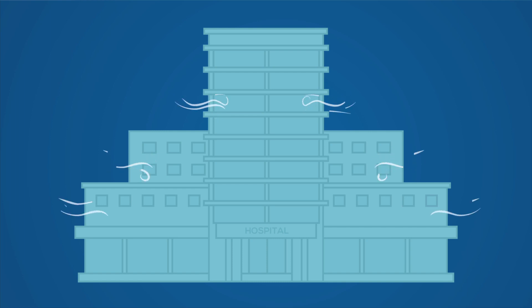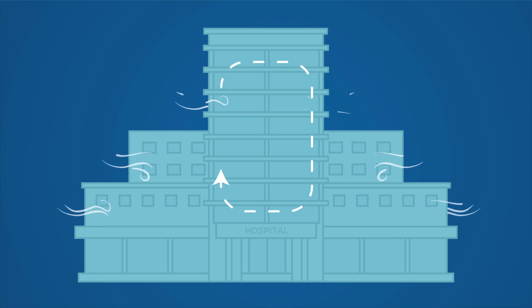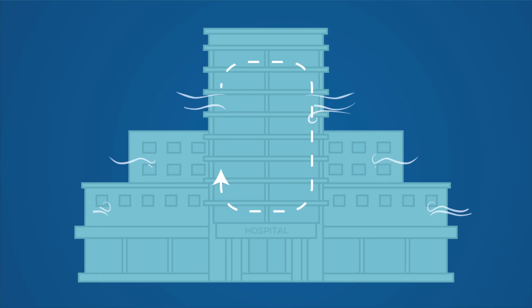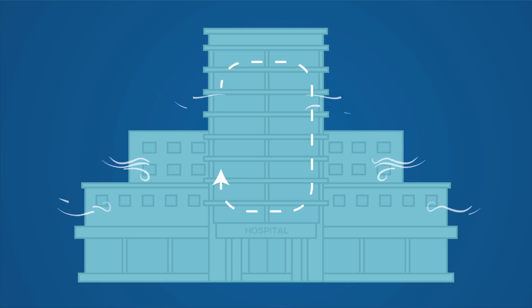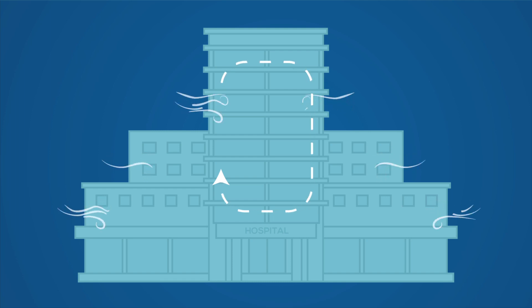When we have a surge of patients in the facility with infectious diseases that can spread through the air, we may increase the amount of outside air to a room or space and decrease how much of the air in that space is refiltered and sent back into the building, by instead pulling that air out of the building. This is a specific strategy to reduce the spread of germs throughout the hospital.